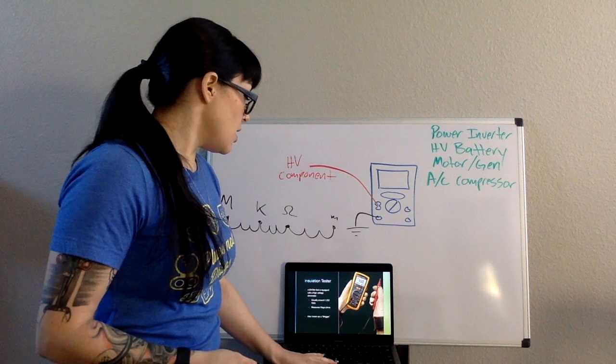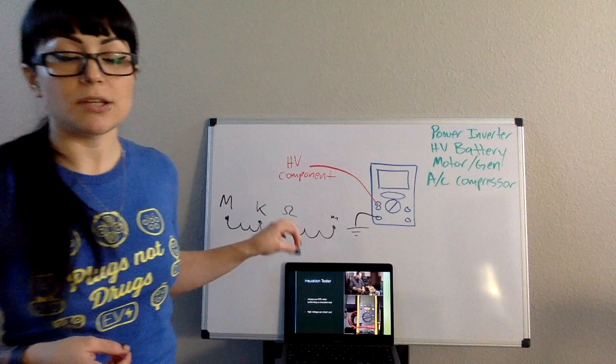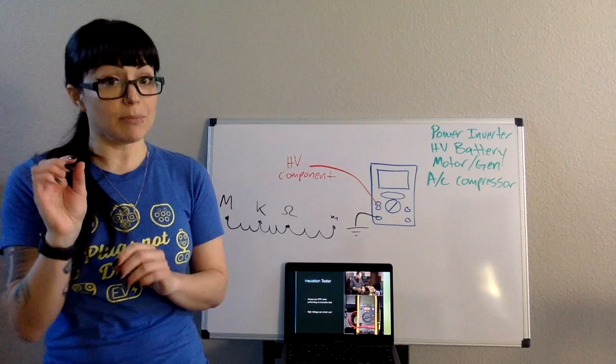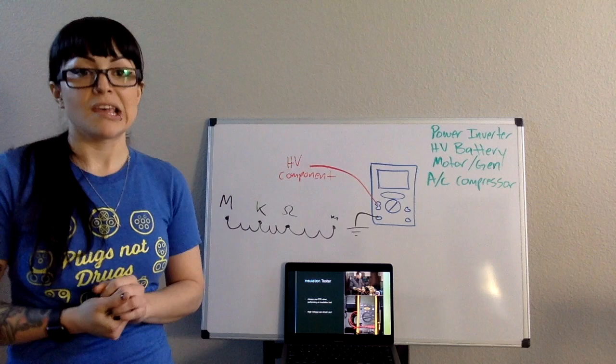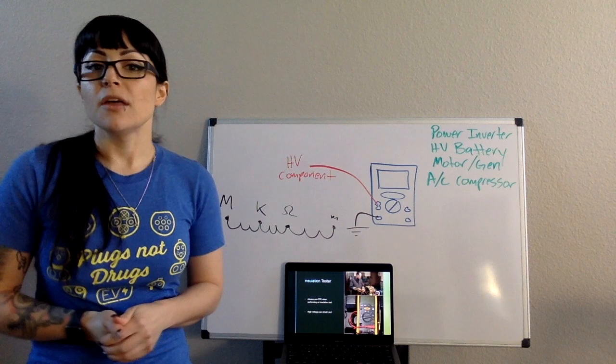Since our meter, in this case for an insulation test, is looking for mega-ohms, it has to put massive amounts of voltage out, very minimal current, but massive amounts of voltage out in order to make that fault show. In this case, it can be up to 1,000 volts, which is not going to hurt you because the current is very minimal.